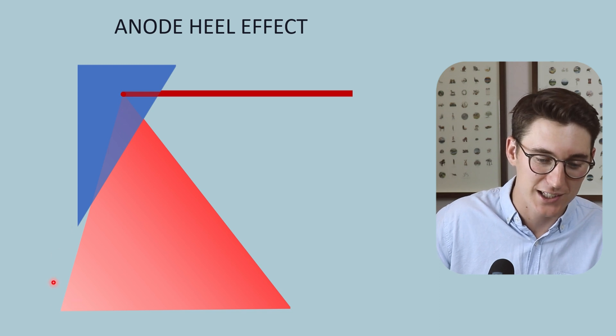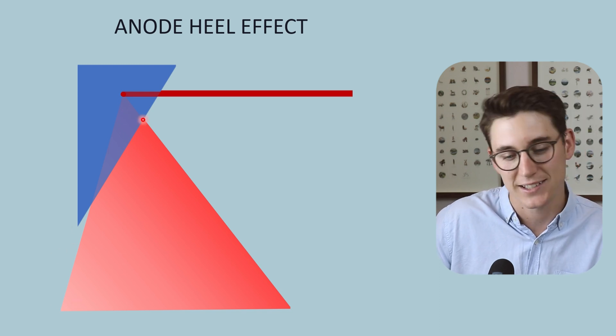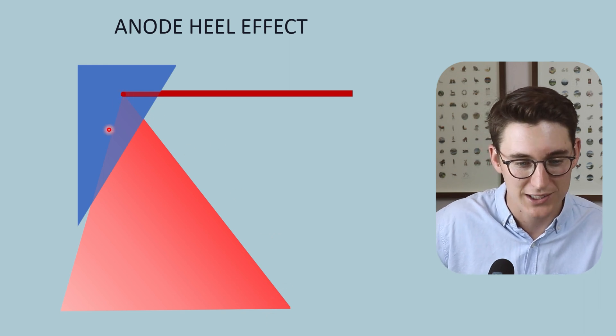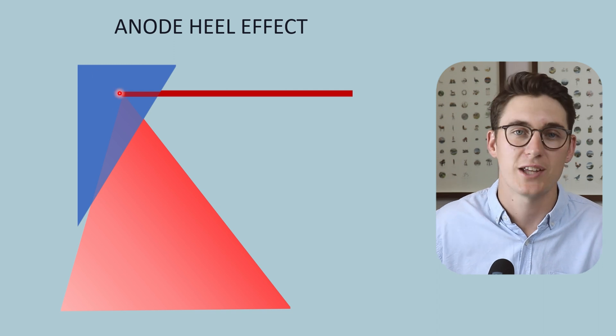The intensity of these x-rays leaving the anode is less than the intensity of those on the cathode side of our field. And that's simply due to the distance that they have to travel through the anode.